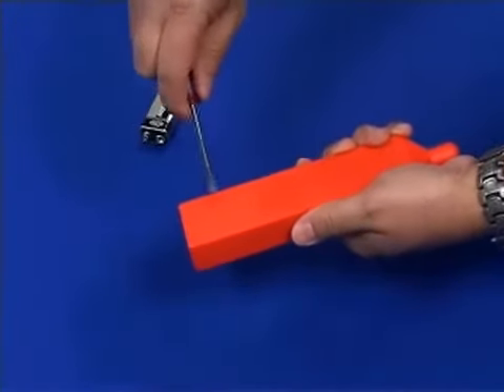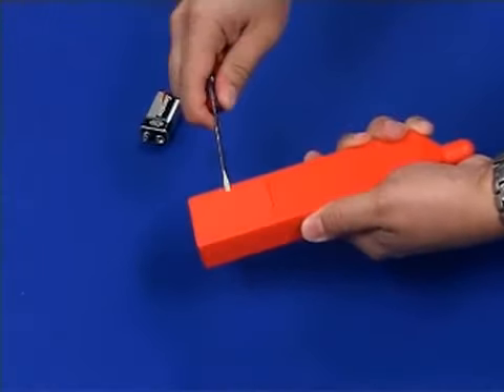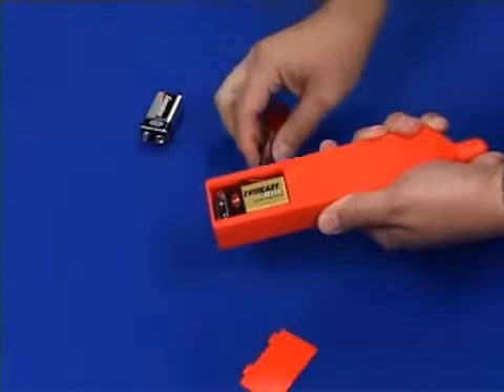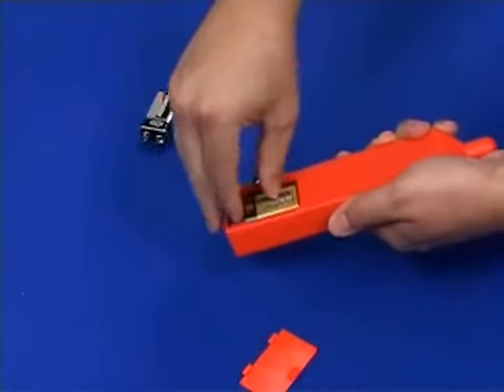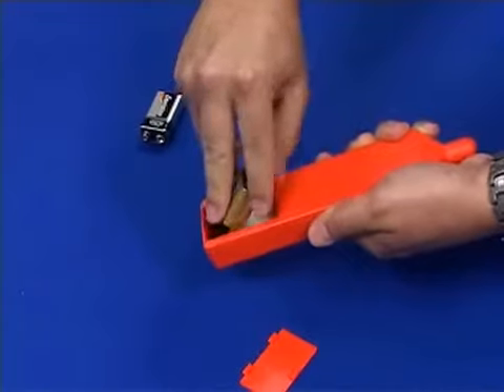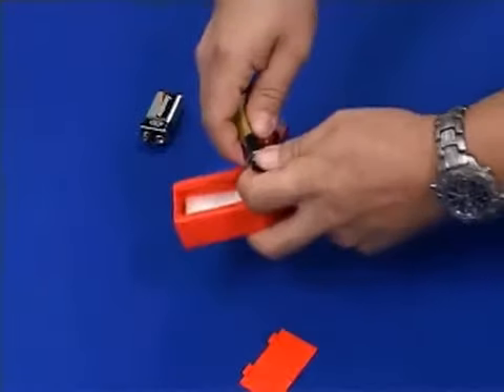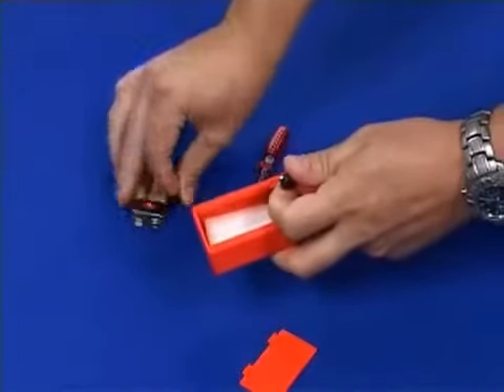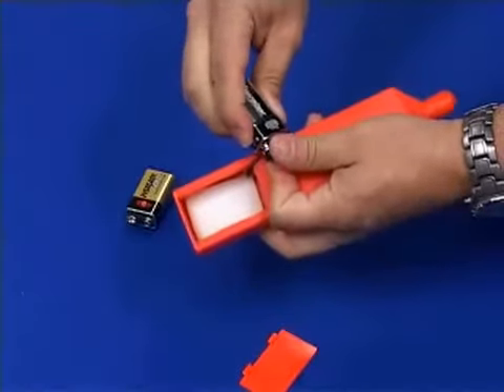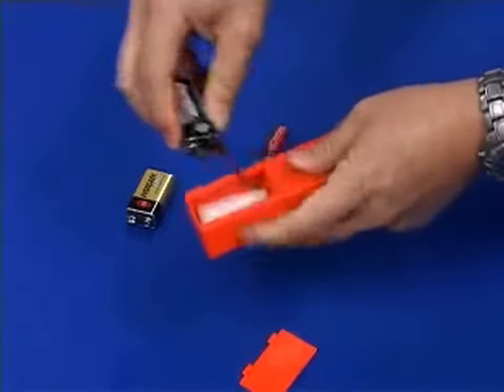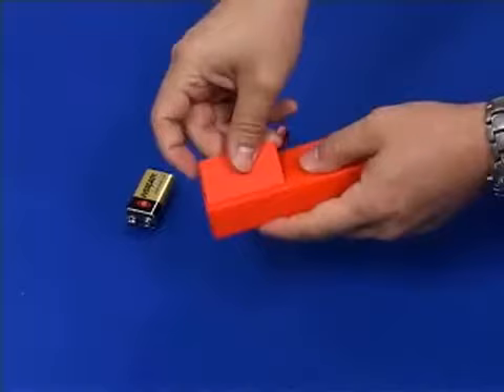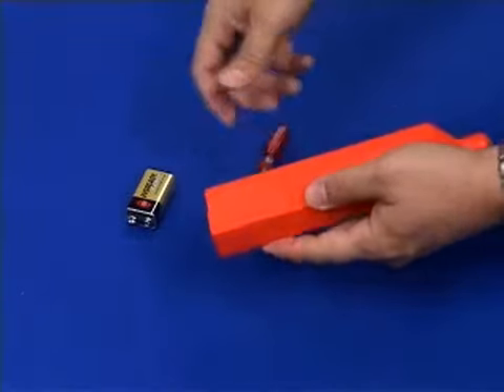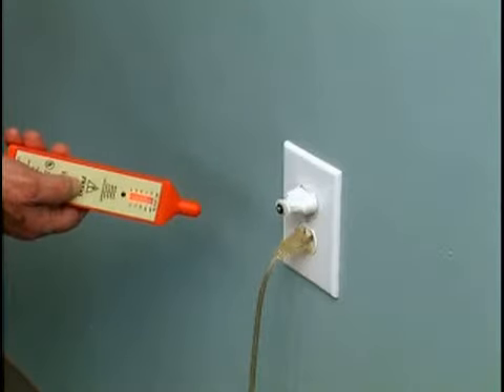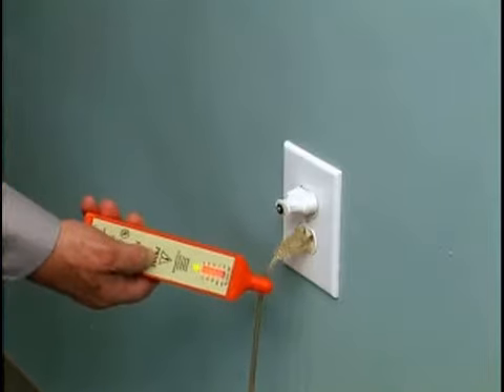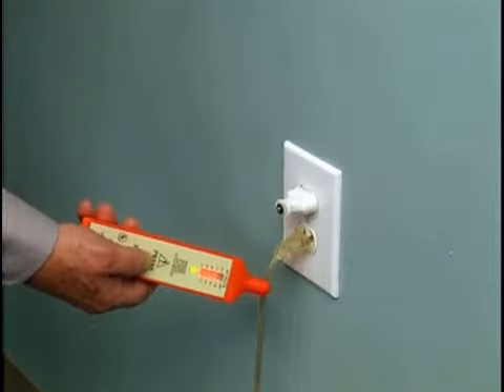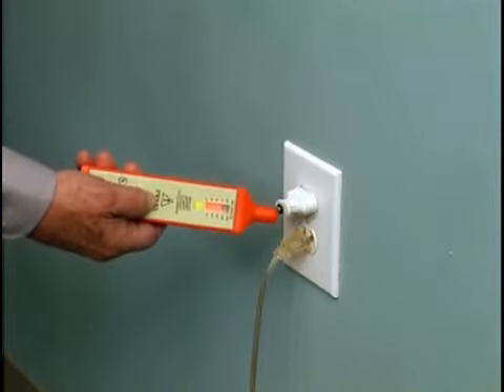To change the battery, you first locate the small slot in the battery cover on the back side of the FVD. Using a small screwdriver, simply pry the cover out. Replace the battery with a good quality 9-volt alkaline type. Replace the cover, and we are again ready to test. Test the FVD on a known AC voltage source when you receive it, then once a month thereafter.